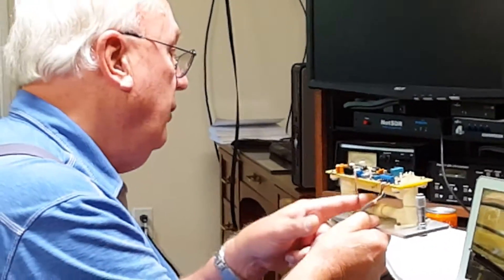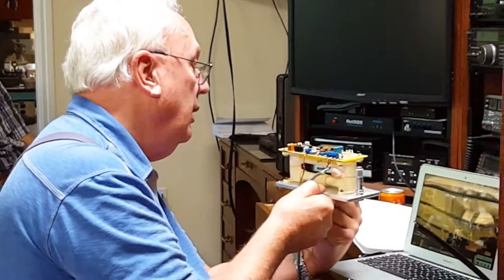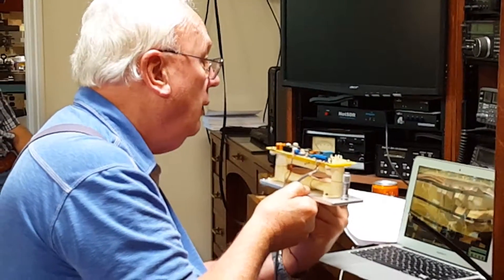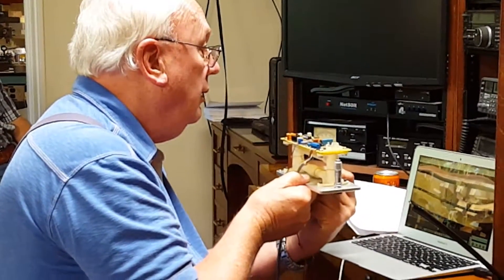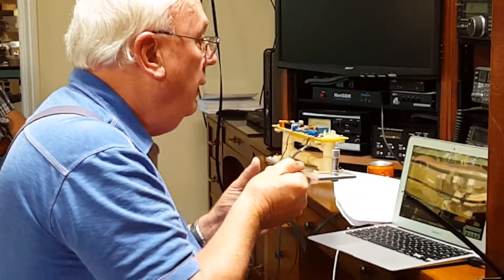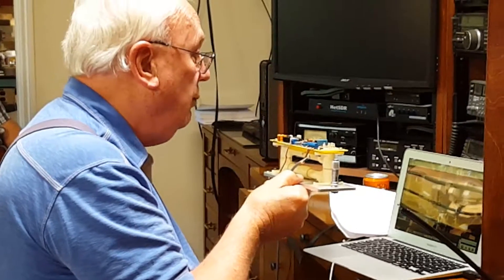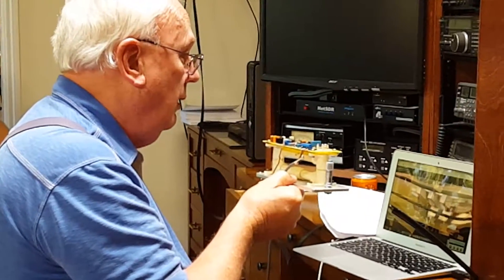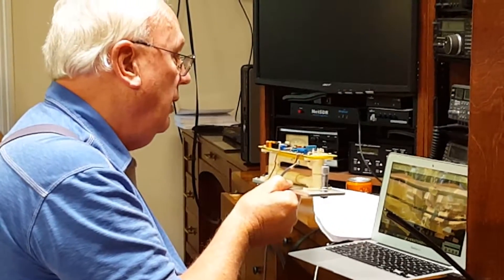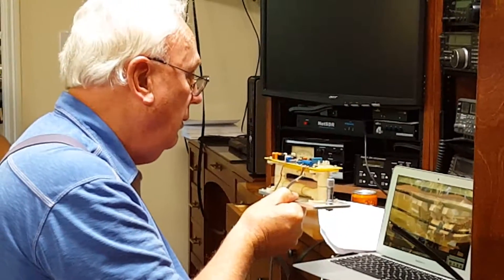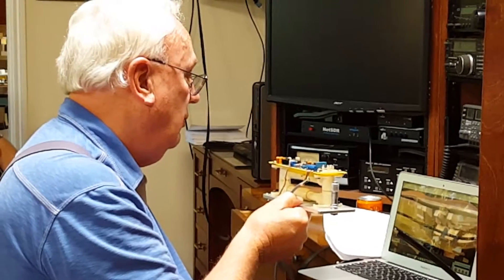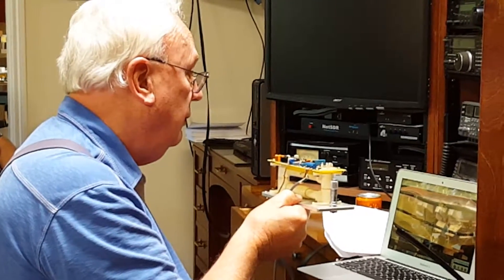In the center, this thing in the center here is the damper and that's a very small hole in there. It's essentially a hydraulic pendulum that's overdamped.